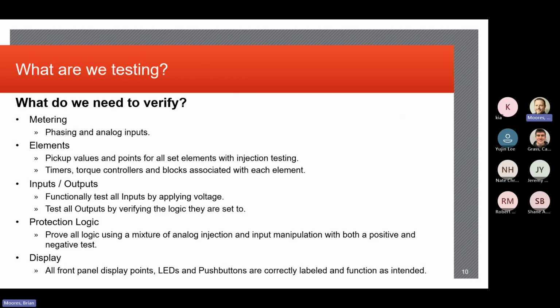There's a whole different set of rules that go along with high voltage, and especially with respect to what the actual voltage is. If it's 13.8 kV, or if it's 230 kV, or 500 kV, 765 kV. So there's a lot of other specifics that go along with that. At 765 and some of those upper voltages, there's not a lot of protection. But there are people with a lot of specialized training, what they're called competent and qualified workers, that are allowed to work on those things. So for testing relays, we're going to work at the control voltage level, 125 volt DC generally, 120 volt AC, and everything's less than 250 volts. So you're going to work in a yard where there's high voltage, but you're not going to generally be up near what that high voltage is.